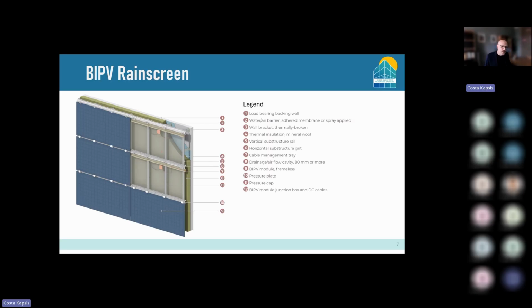Typically, for the building scientists in today's presentation, you might be familiar with other materials that in conventional construction are precast concrete. It could be an aluminum or a composite panel. In this case, we're using electrically active envelope modules, right? The BIPV modules. The difference with these modules is that they come with a junction box on the back and two cables, a positive and a negative cable, that carry the DC electricity. Most of the time we connect these modules in series in a daisy chain effect. And then we bring that cable through a dedicated penetration in your envelope into our electrical system to connect it to an inverter. And the job of the inverter in the electrical room is to take the DC electricity from our modules inside our building and invert it to AC, which is the type of electricity we're using in our building, right?